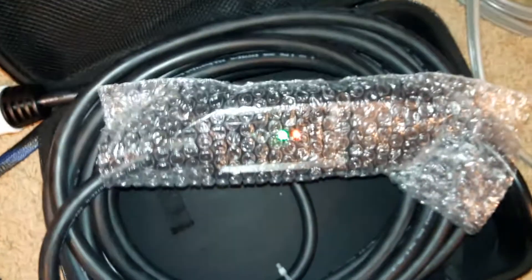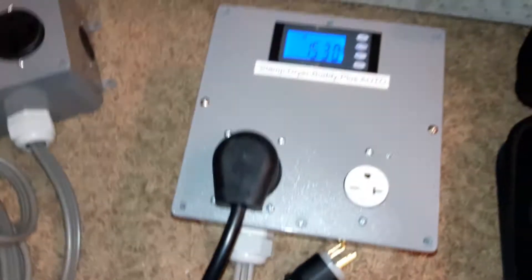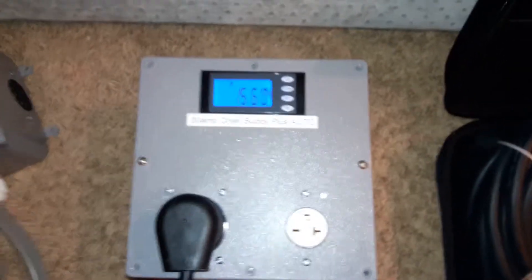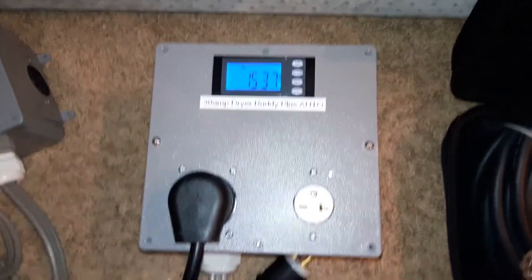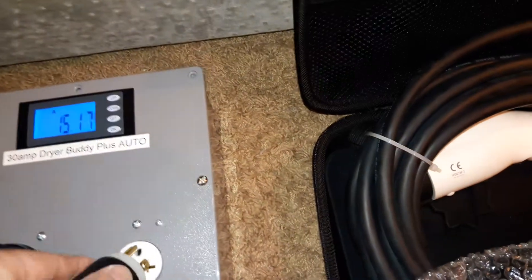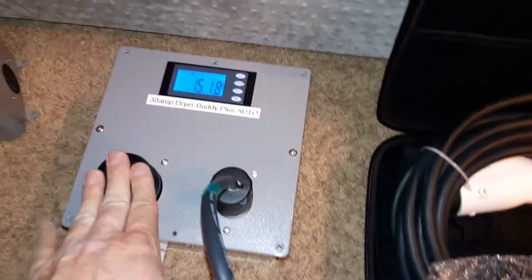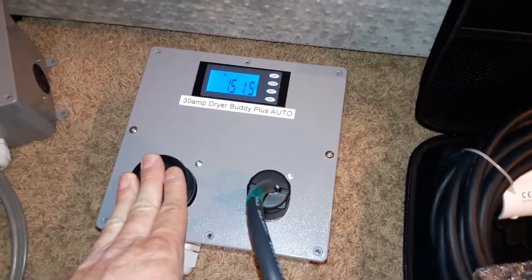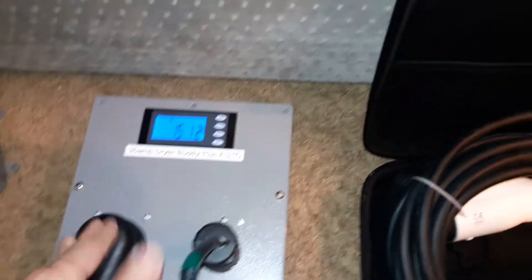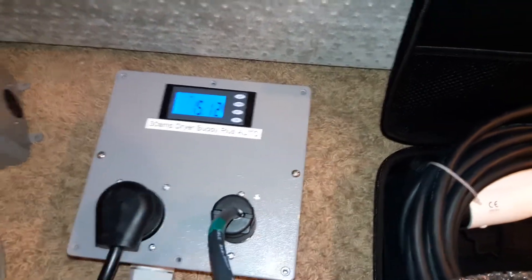This is plugged in and it's showing that it's connected and charging, and we can see the vehicle drawing amperage here, and the EVSE outlet has turned off. In this application we're showing how you could actually charge two different EVSEs with priority. This outlet is always live and always has priority — we would call this the master. This is the slave.